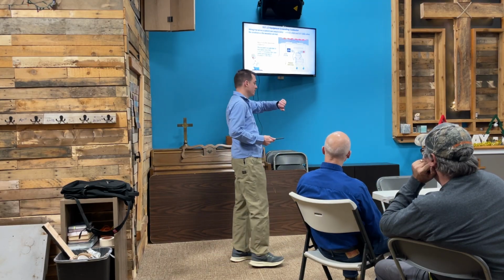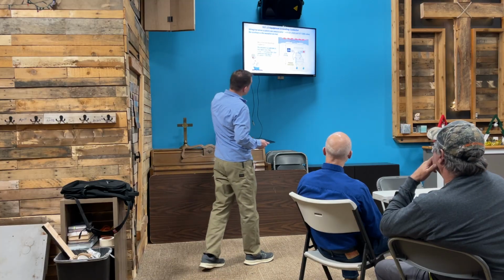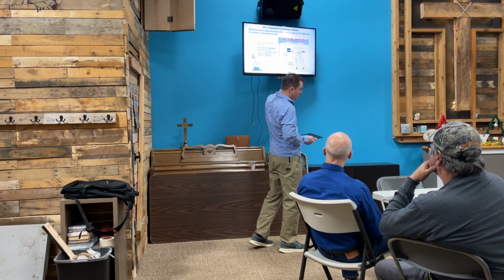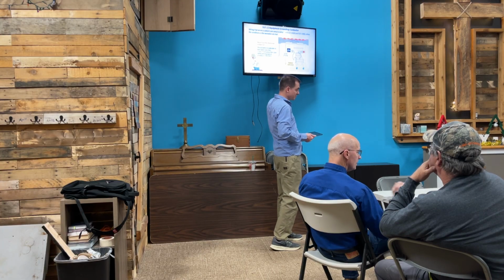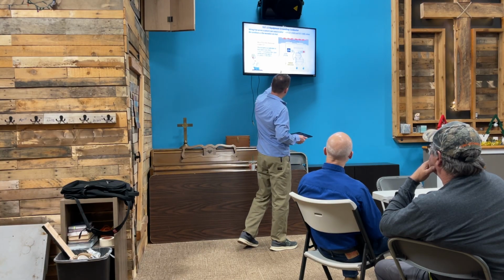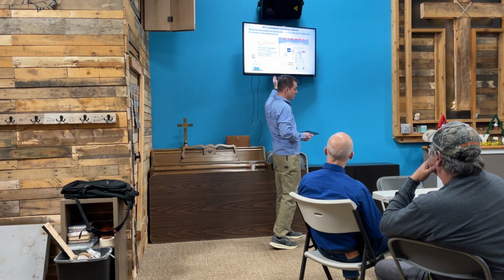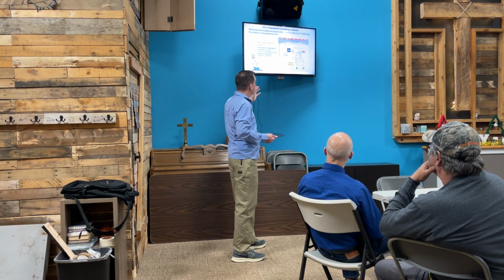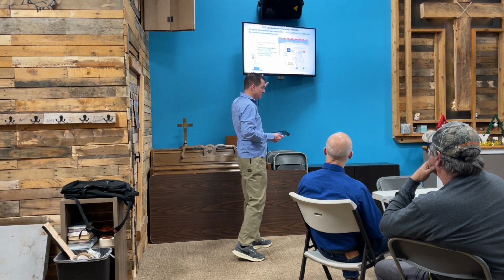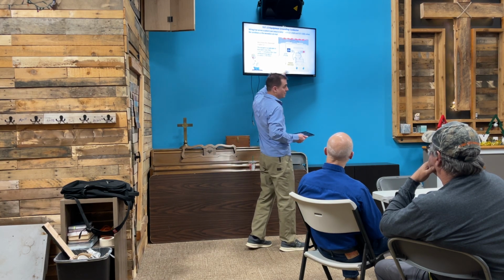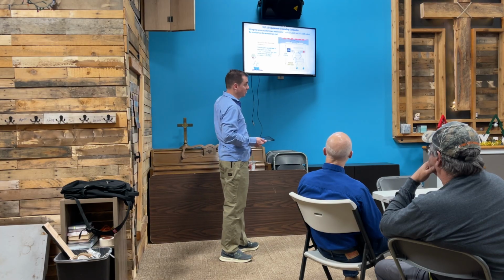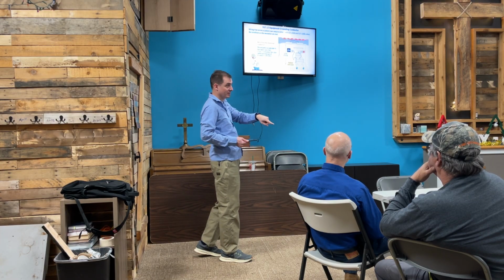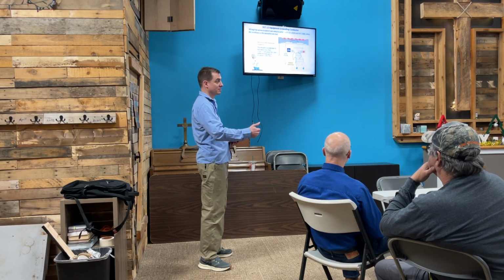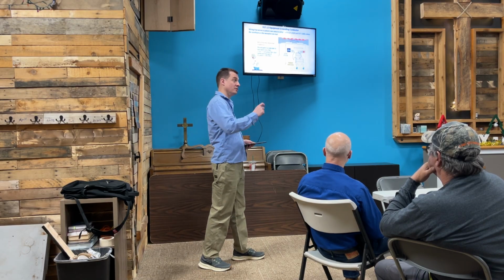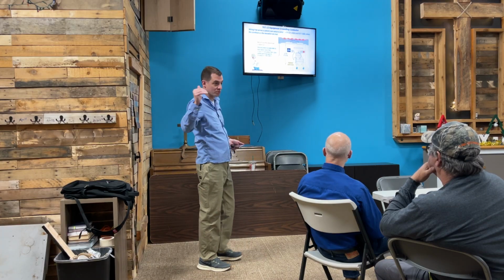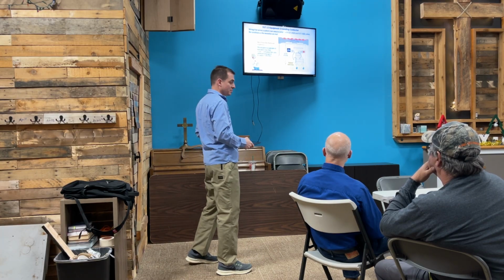So keep looking there, Joe, I'm gonna keep going for time's sake. So the point of this is, whether we agree or don't agree, ask your inspector, or your inspector tell the contractor whether both the switch and the light have to be out, or one is good, one or the other. But let's say by chance the light switch and the lights were both outside of the patient care vicinity, you only have to follow A or B, which is the very last point of that exception, the very last words there. So you can use a raceway if you want to, or just the conductor if you want to, if both are outside of the space.